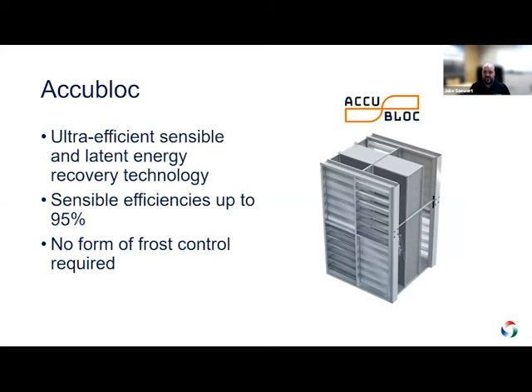So again, I know that's a very, very brief overview. Usually we give this presentation in an hour or so and get really deep into how it works and more information on it. But think of ACCUBLOC as just another option of energy recovery that's very, very efficient, great for electrification efforts, very high sensible efficiencies. It can do 95%, but truthfully 90, 91 is probably the sweet spot. And then you really don't need to worry about any type of frost control. So this can operate down to very, very cold temperatures.